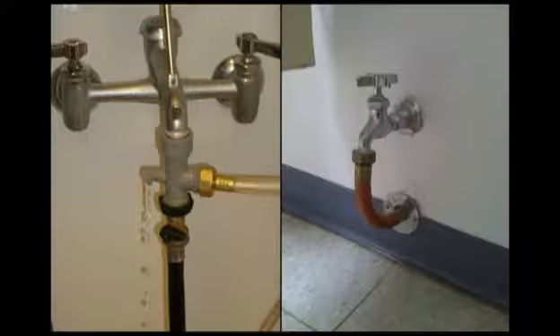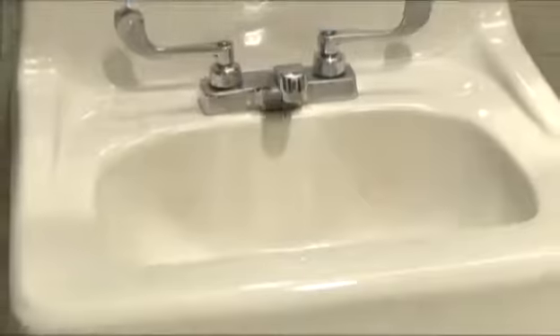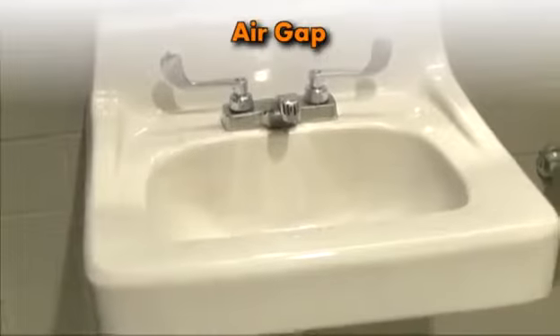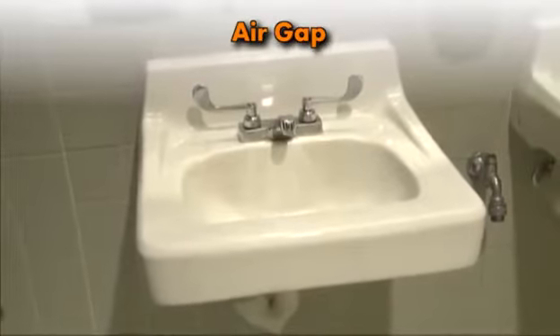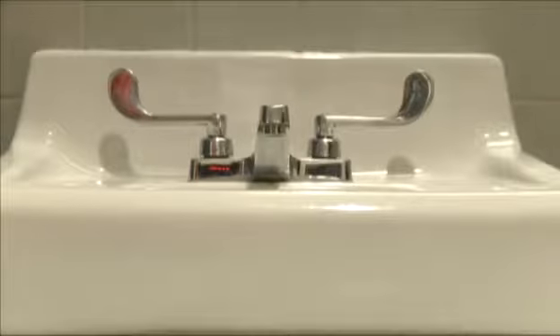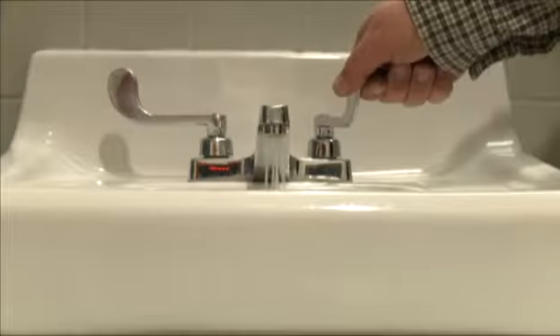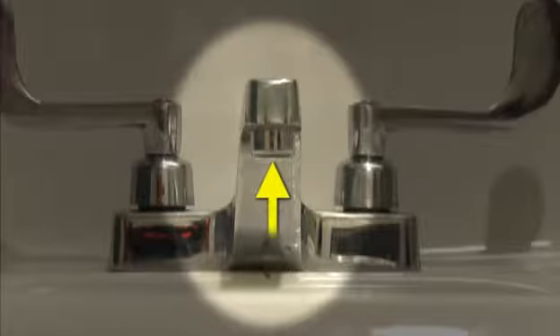So how can you protect your drinking water? Never leave a hose attached to a faucet that doesn't have a hose bib vacuum breaker or an air gap. Air gap is the safest and simplest way to prevent a cross-connection by a physical separation between a potable water source and a potential contamination. In general, the air gap must be twice the supply pipe diameter, but never less than 1 inch.